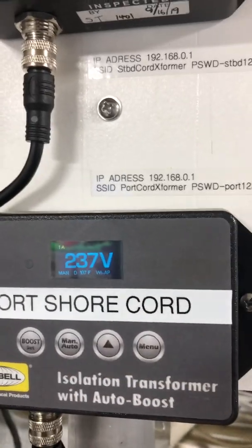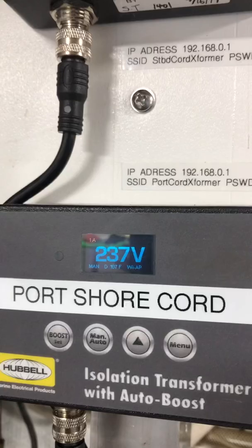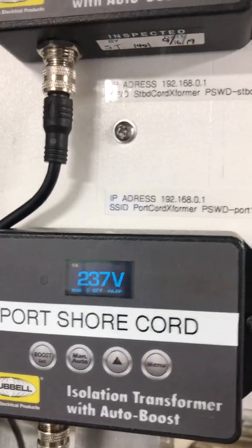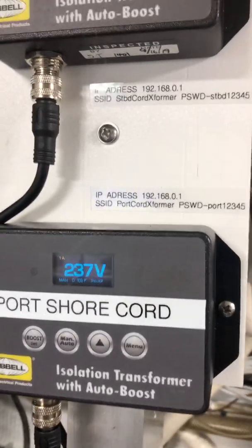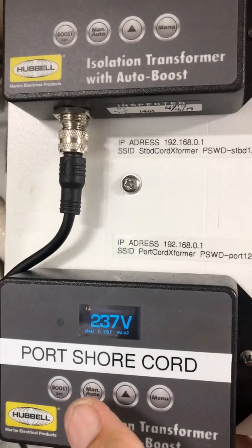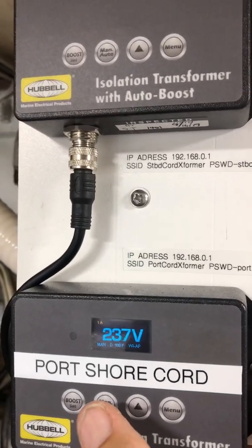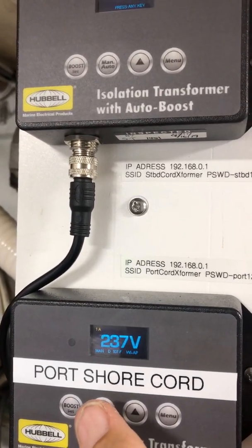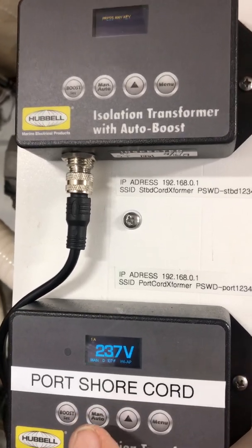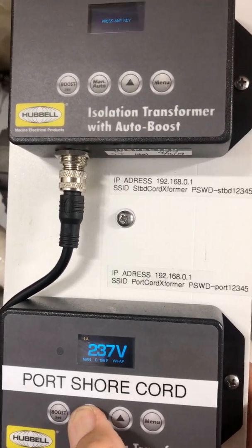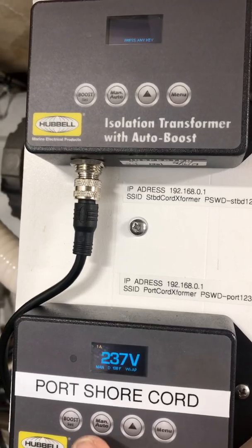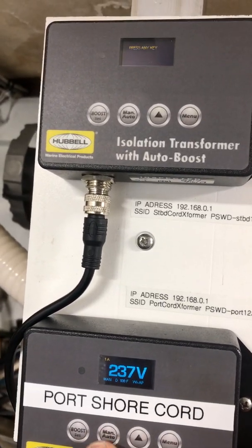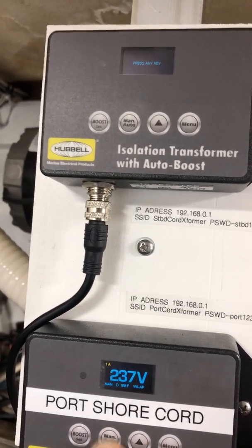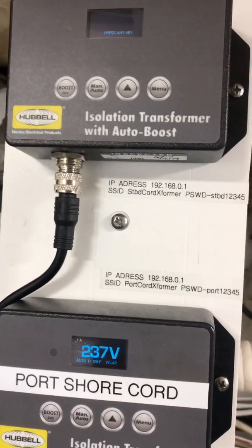Notice we're getting a voltage too high. Our boost threshold is set at 215 volts. If you try to set the unit into the boost mode with it above 215, you'll get a voltage too high setting. We're going to put it back into the automatic mode. And that's done by pressing the manual auto button. And it sometimes takes more than one attempt.